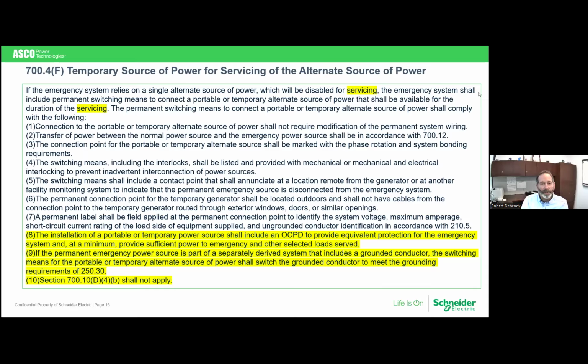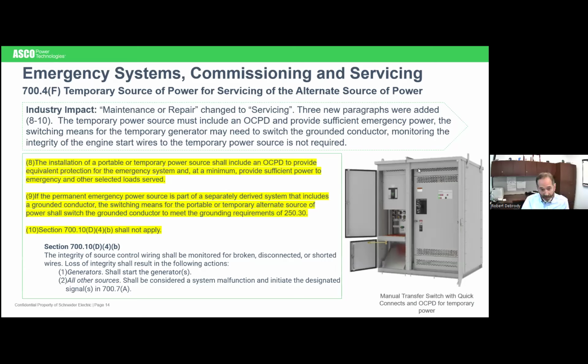Number 9 talks about separately derived systems. They want to make sure that this temporary generator has that same type of switching of the grounded terminal as the permanent source did. And the 10th one here talks about a section that they say will no longer apply. So let's jump back up. And down at the bottom of this slide, you can see what that section is that they say shall not apply. And that's just telling you that the integrity of the wire, that start signal out to the generator, you don't have to monitor that if you're hooking up a temporary source. I guess it's kind of difficult to maintain that checking of those wires when you've gone from a permanent source to an alternate source. So it's understandable why they might say that you're exempt from annunciating and starting the generator if there's a break in that start signal cabling.